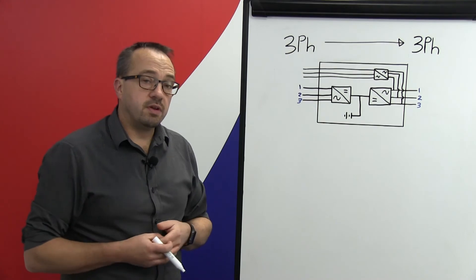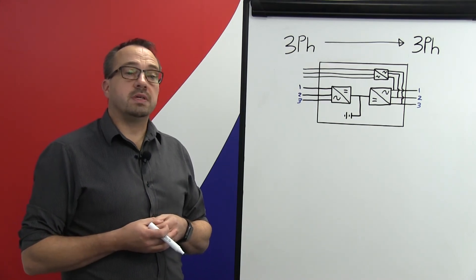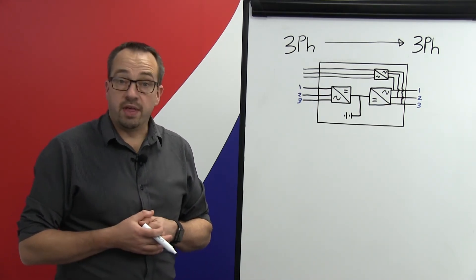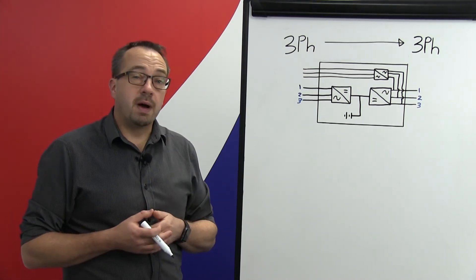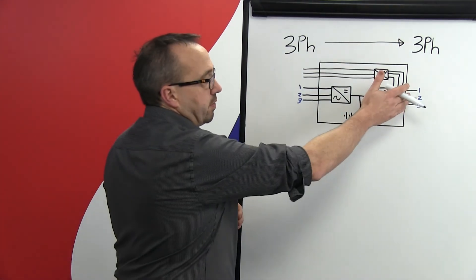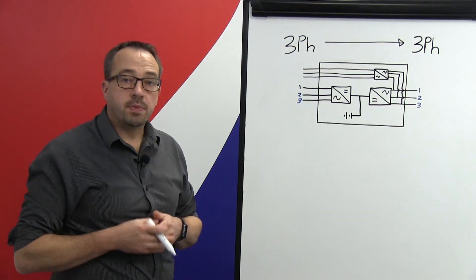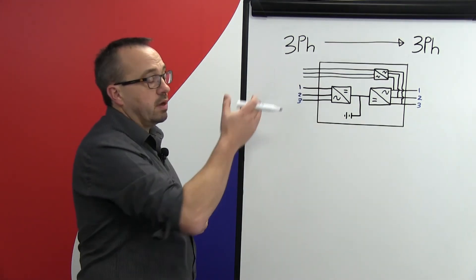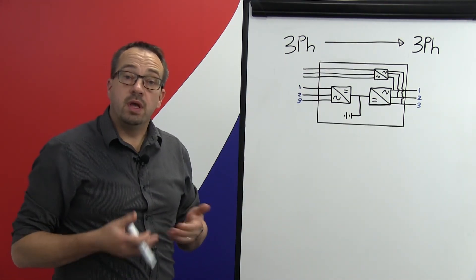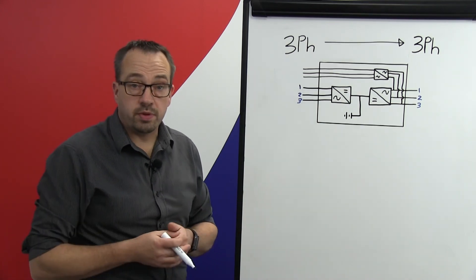Now obviously we must consider most online dual conversion UPS systems do have internal static bypass switches and therefore if the UPS system is in bypass then any imbalance on the outgoing side of the UPS system will be passed through directly onto our input supply and therefore the infrastructure must be designed in order to support this.